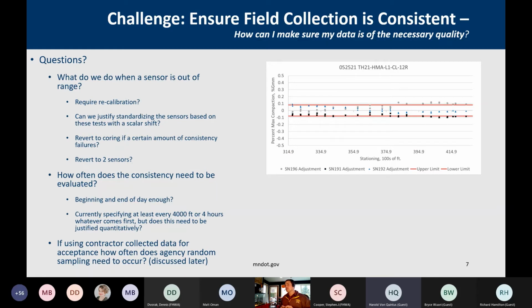This gives an example of one of those situations. We could also put up some of those plots Craig was showing in Ohio, an example where we need a plan if something like this happens: sensor 196 was in spec at the beginning of the day, and by the end of the day it was measuring too low, so it had to be corrected.